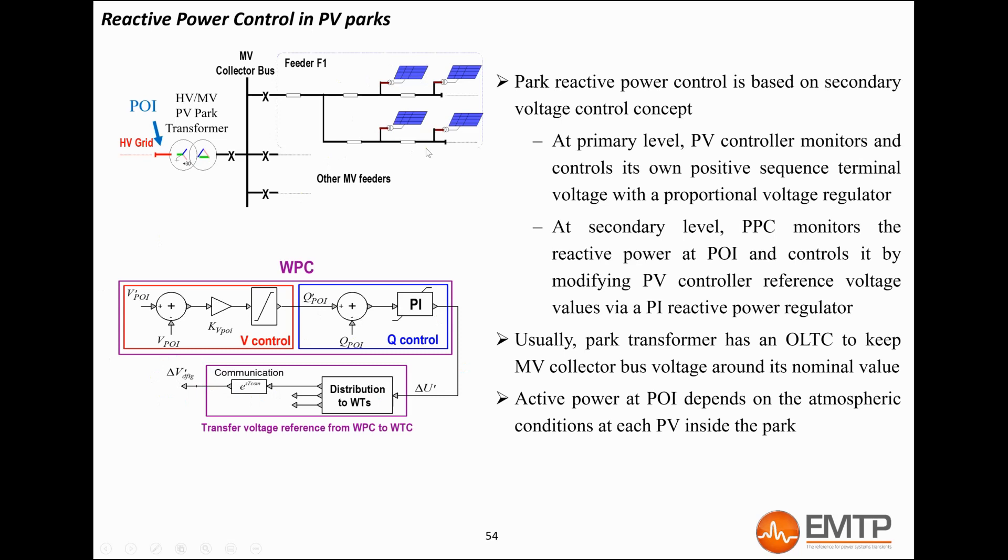By default, controllers control the voltage to one per unit. If the PPC commands more reactive power, it sends a positive voltage deviation reference and the converters end up producing more reactive power.